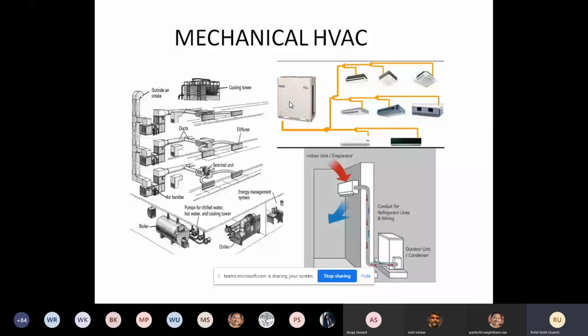On the left is the original system. This is what was designed by Willis Haviland Carrier maybe 100 years ago, and that's how the air conditioning system started. It's called a chilled water system. Chilled water is produced in a chiller plant room, maybe placed somewhere in the basement, and the heat from the building is actually expelled to the atmosphere through cooling towers. So it's a central system.